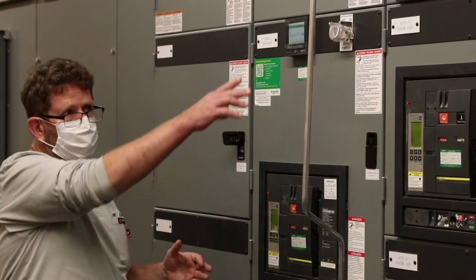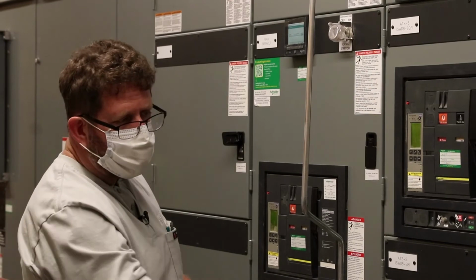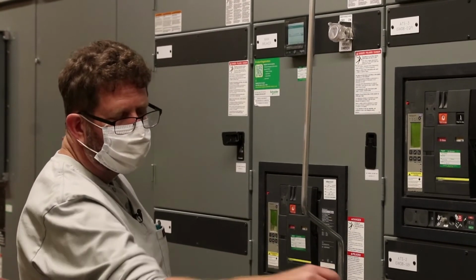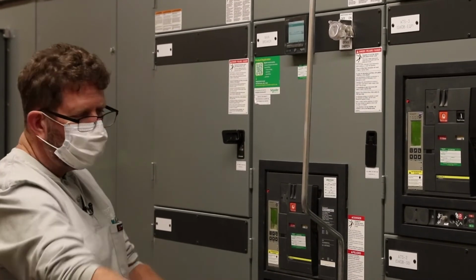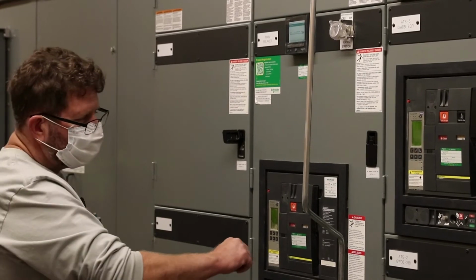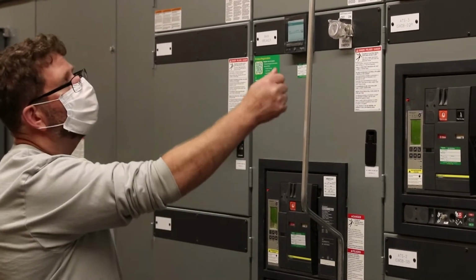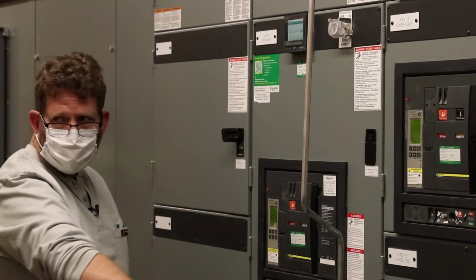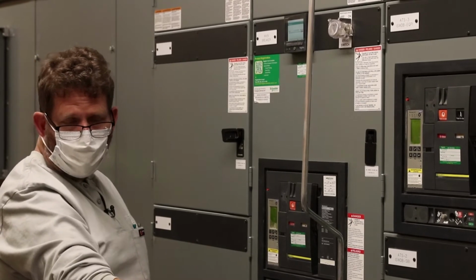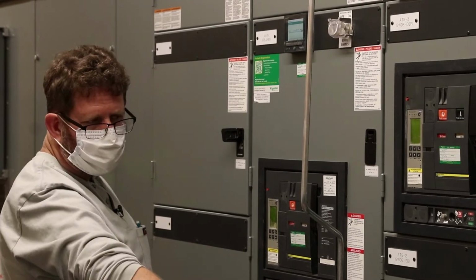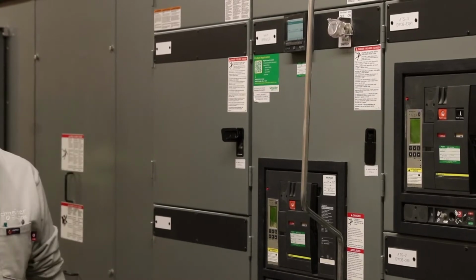The reason you would do that is if you're working down here, racking a breaker in or out, doing voltage checks, anything working downstream of this, you'd set it to on, and that would minimize the arc flash values that you could be exposed to downstream of this main breaker.